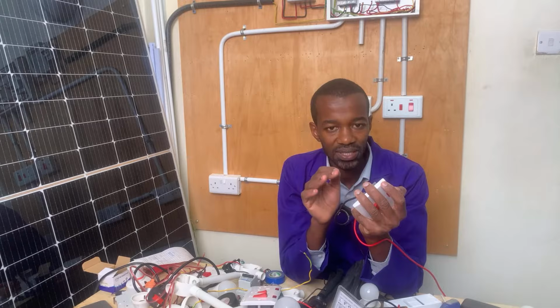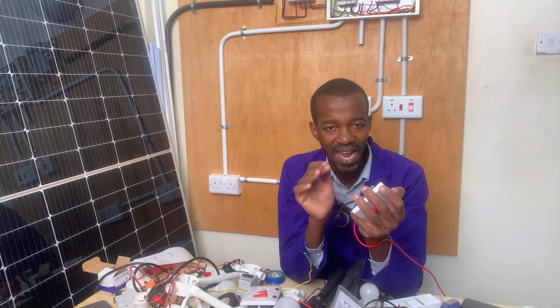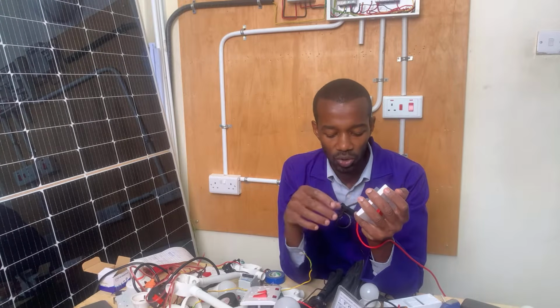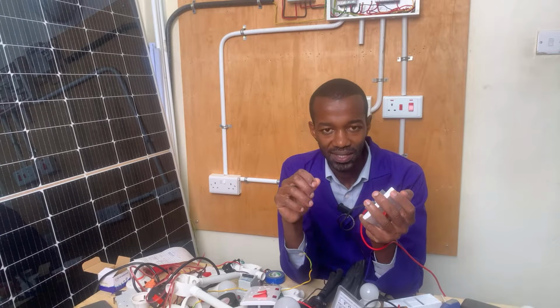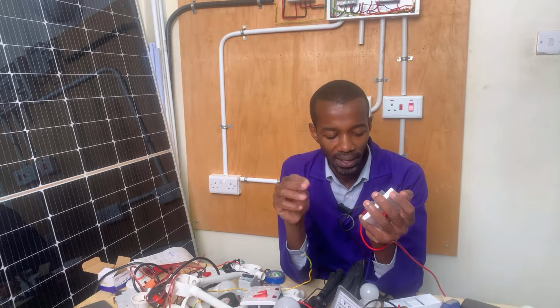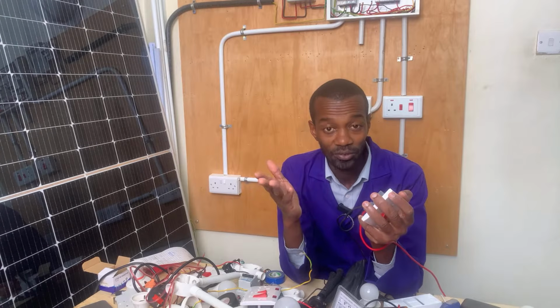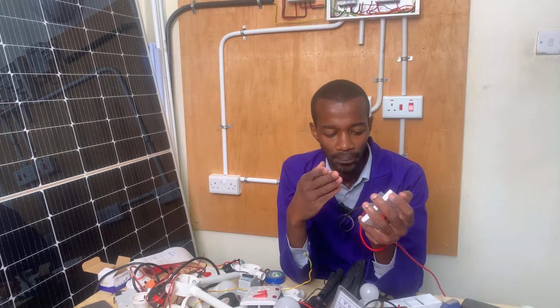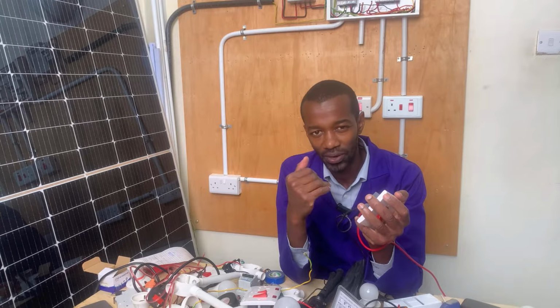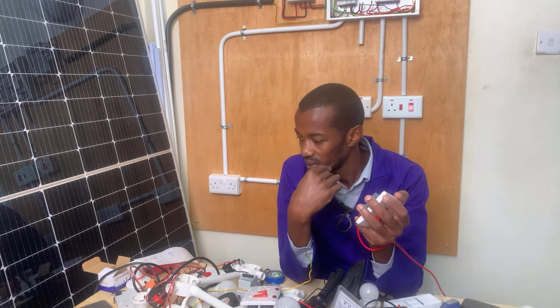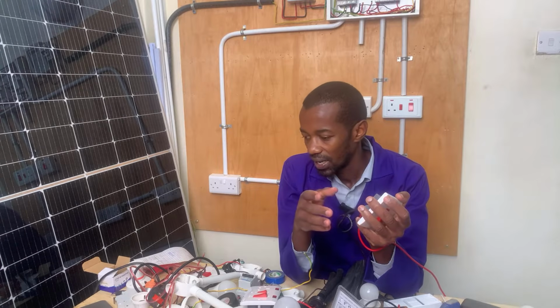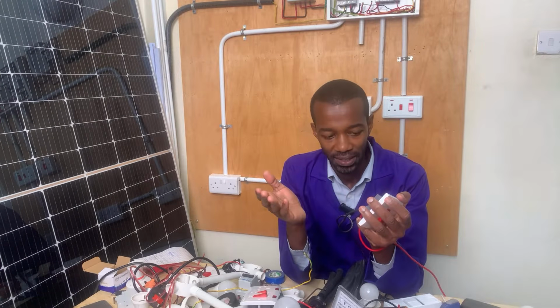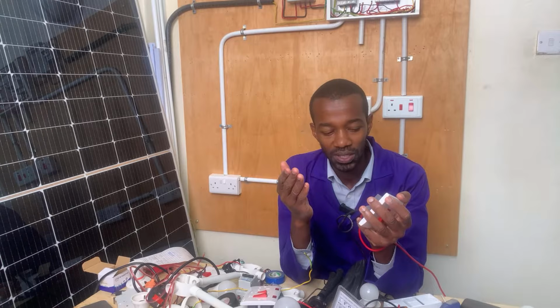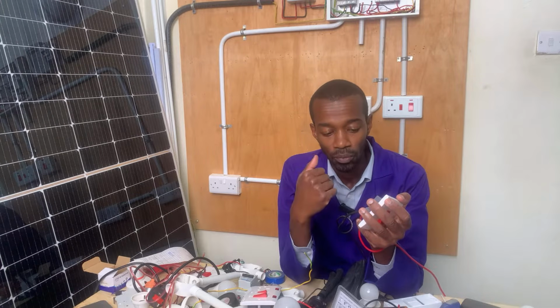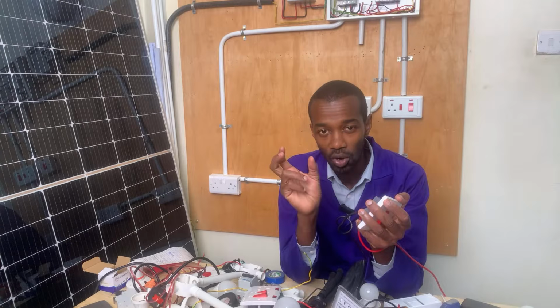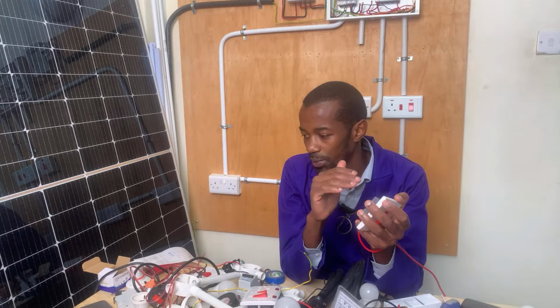Another thing I've noticed people do is use undergauged cables. If you're supposed to use a 4 or 6mm cable and you use a 2.5 instead, there's a problem, because that circuit draws a lot of current, assuming it's a geyser or an instant shower head. It requires more current, and that 2.5 cable will start overheating. Overheating is dangerous for electrical gear such as a DP switch.